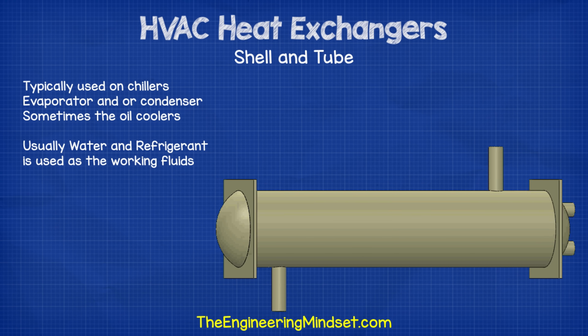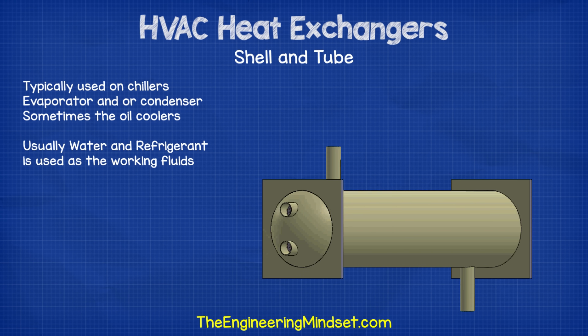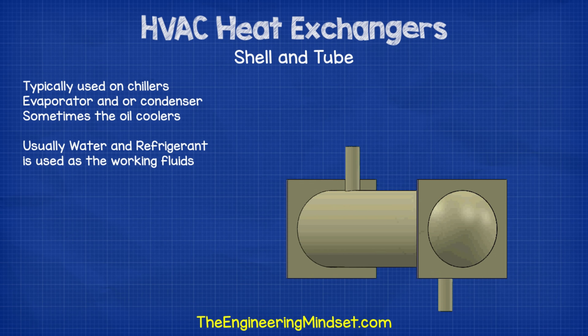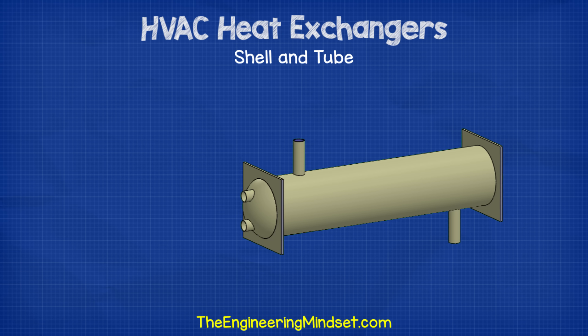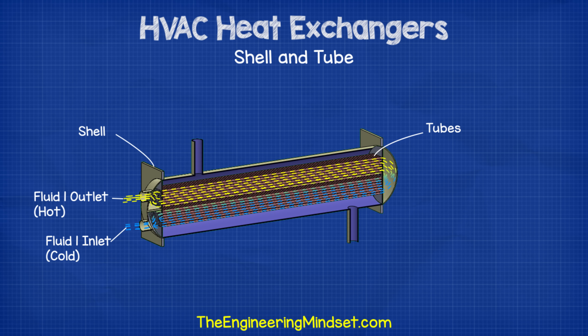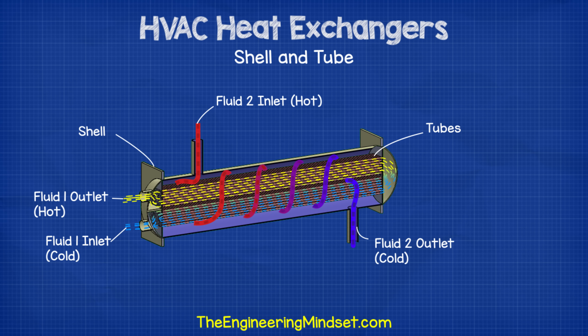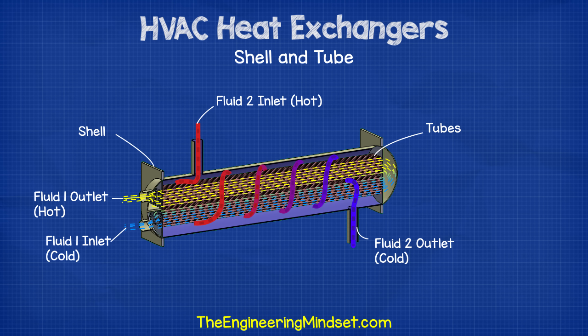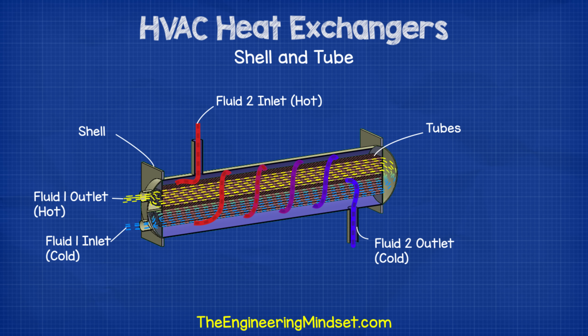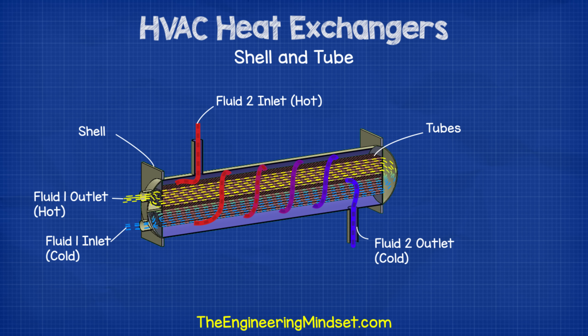Shell and tube heat exchangers are typically found on chillers for the evaporator and/or condenser, and sometimes for lubricating oil cooling. They have an outer container known as the shell, with a number of pipes known as tubes sitting inside. The tubes contain one fluid and the shell contains another; the two fluids are always separated by the tube walls and never mix. The temperature difference between the fluids causes thermal energy to transfer through the tube walls. When used as an evaporator or condenser, the two fluids will be water and refrigerant.